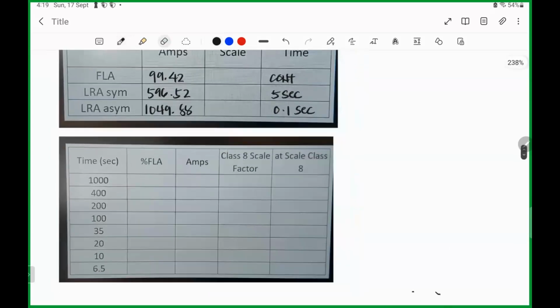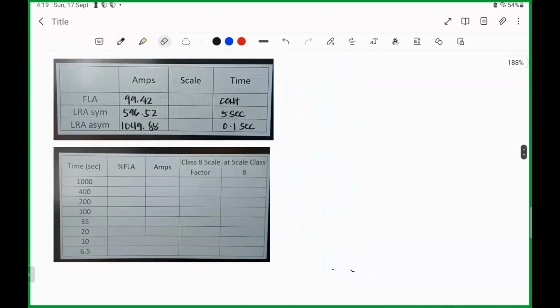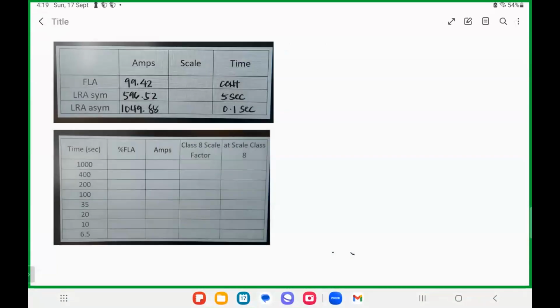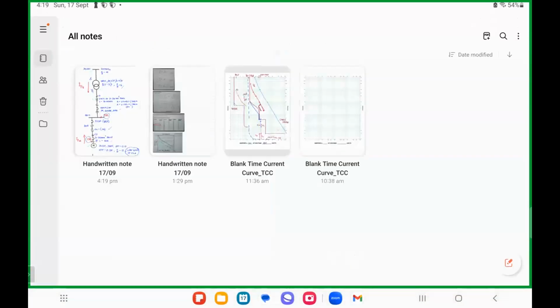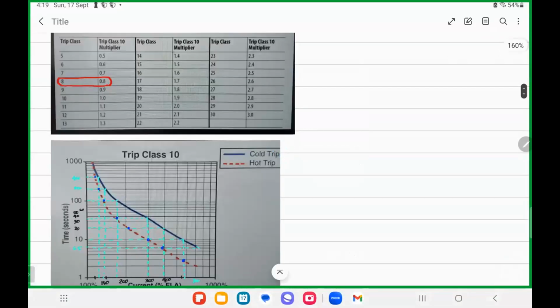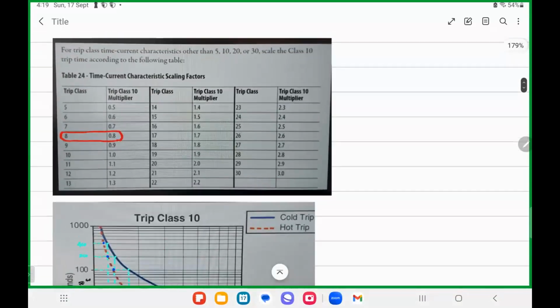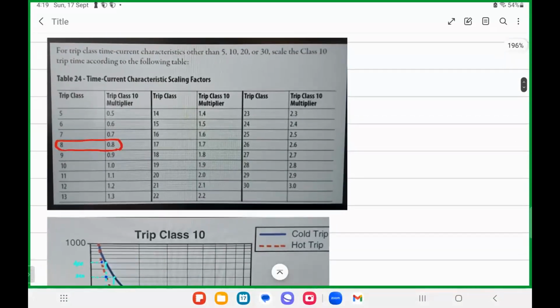Okay? Now, let's discuss the overload relay. Meron akong table na ginawa na kanina, para yun na lang gamitin ko, mabilis tayo. So for overload relay, I choose the trip class 8 and the trip class 10 multiplier. Now, you can double check kung capable na or pwede na sa inyo yung 7, 6 or other trip class. But definitely kung mas bababa kayo, didikit yung line ng overload relay nyo doon sa motor curve.